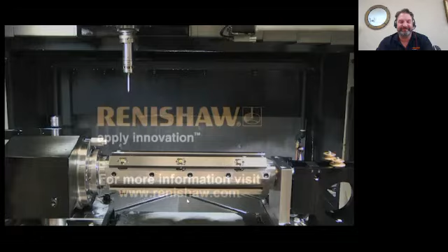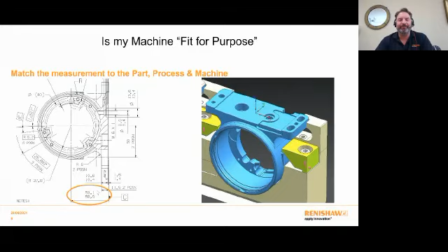So the point of that is that we implement that particular health check every time we make a part and every time we run a process, because it has an impact. Knowing where that rotary axis is, is absolutely critical. When we're making a part, I know I've got a key dimension here that I need to hold, and that is this face relative to the center of this bore. That is a function of the work offsets, and it is a function of the rotary axis of the machine. So if I'm to hold plus or minus 100 microns, this is about what do I need to control. Is that rotary axis good enough and repeatable enough to enable me to hold that? Can I then make sure that my work offsets and the tool offsets that I'm using, which are things that machines are using, are good enough to hold it? So what we're also doing is some long-term measurement as a result.